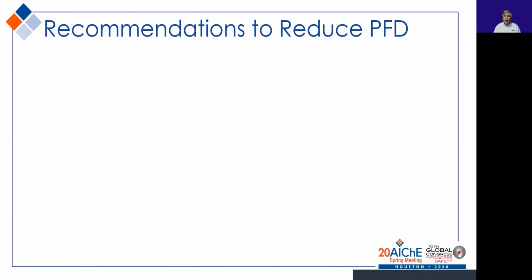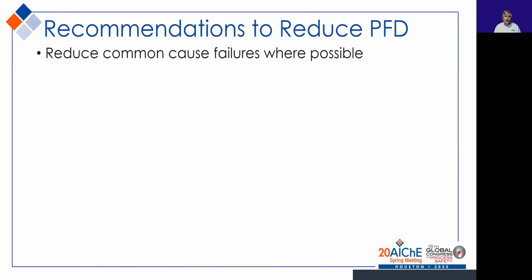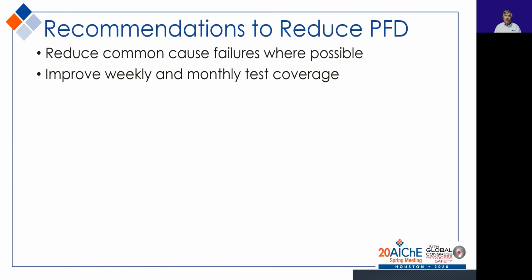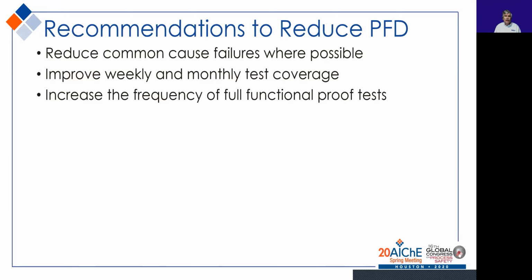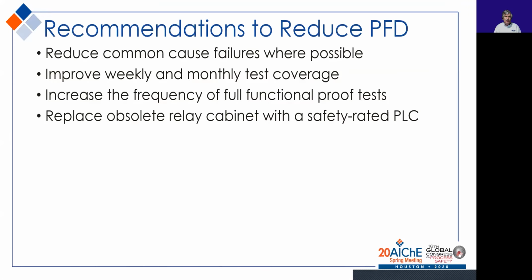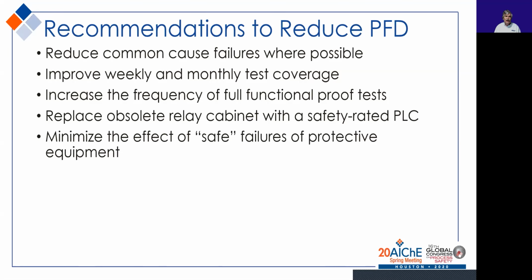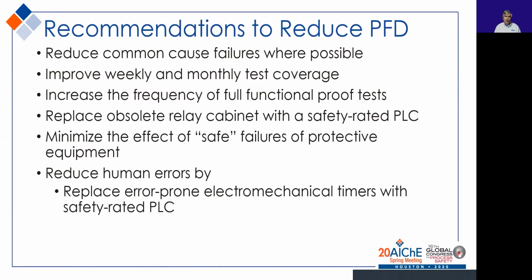Recommendations to reduce probability of failure on demand came from examination of the fault tree. We need to reduce common cause failures wherever possible. We need to improve the weekly and monthly test coverage. We need to increase the frequency of the full functional test; we recommended once per year. We need to replace the obsolete relay cabinet with a safety-rated PLC. We need to minimize the effect of safe failures of protective equipment. We need to reduce human errors by replacing the error-prone electromechanical timers with a safety-rated PLC.